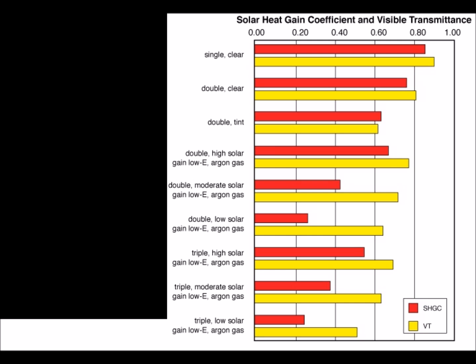Let's look at light to solar gain. Light to solar gain is the ratio between the SHGC and the VT. It provides a gauge of the relative efficiency of different glass or glazing types in transmitting daylight while blocking heat gains. The higher the number, the more light that's transmitted without adding excessive amounts of heat. This energy performance rating isn't always provided.